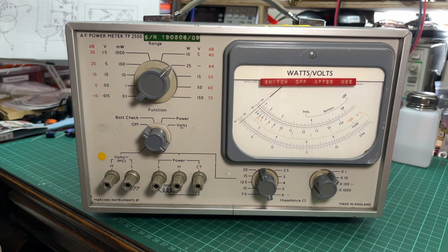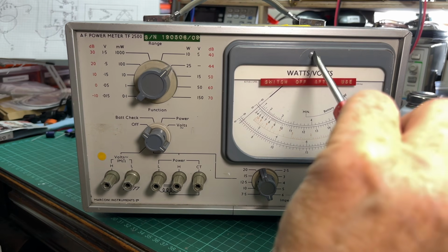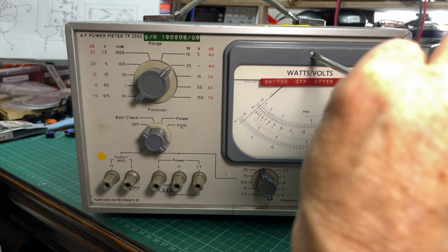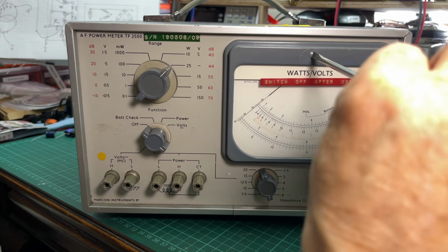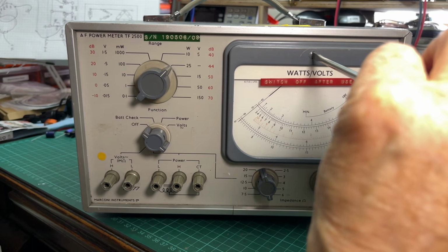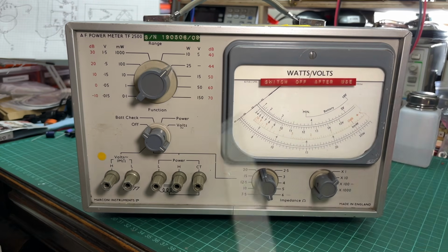One of the first things I always like to check when I get a new instrument like this, it's always a bit of a lottery obviously when you're buying them online, is whether or not we can adjust the meter, so we do actually have some meter connection to the needle, and we do, which is good news. So I think the first order of operation is we'll turn it around and have a look at the battery compartment, have a look at whether it's got batteries. I suspect it has because it's really heavy.